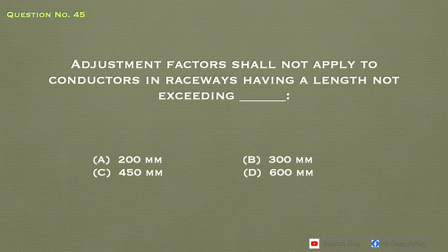Question number 45. Adjustment factors shall not apply to conductors in raceways having a length not exceeding blank. A. 200 mm, B. 300 mm, C. 450 mm, D. 600 mm. Answer: D. 600 mm.